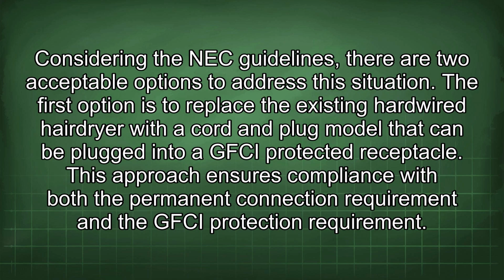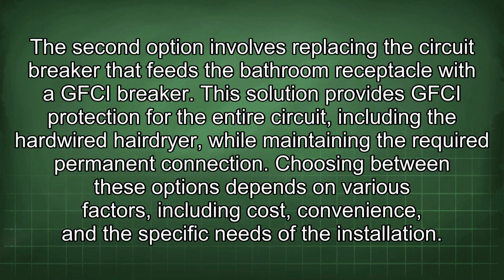Considering the NEC guidelines, there are two acceptable options to address the situation. The first option is to replace the existing hardwired hairdryer with a cord and plug model that can be plugged into a GFCI protected receptacle. This approach ensures compliance with both the permanent connection requirement and the GFCI protection requirement. The second option involves replacing the circuit breaker that feeds the bathroom receptacle with a GFCI breaker. This solution provides GFCI protection for the entire circuit, including the hardwired hairdryer, while maintaining the required permanent connection.